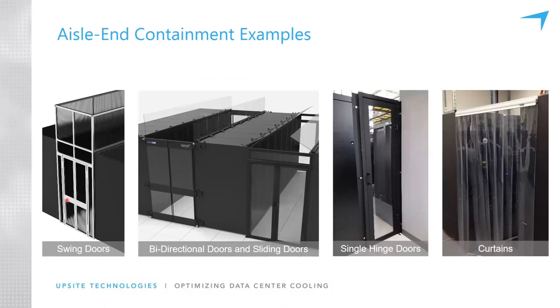On the far left here, we've got swing doors. These are bi-directional doors that swing inward and outward, mounted in a frame. They happen to be attached to a chimney here for a hot aisle application. In this image, there's another bi-directional door that attaches magnetically. These are sliding doors with a transom to match the height of the cabinets. And so these doors slide left and right.